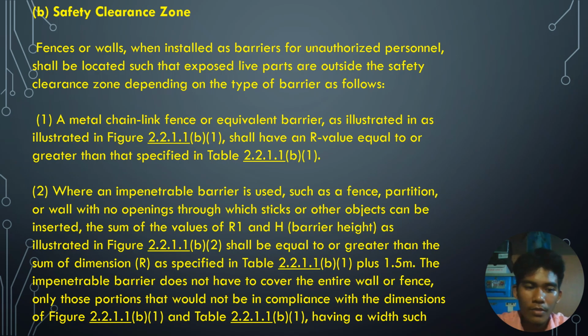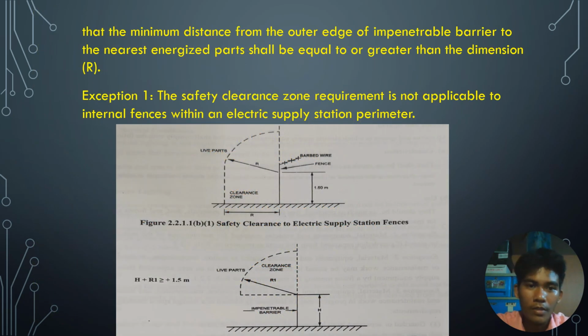in compliance with dimensions of Figure 2.2.1 and Table 2.2.1, having a width such that the minimum distance from the outer edge of the impenetrable barrier to the nearest energized part shall be equal to or greater than the dimension. Exception: the safety clearance zone requirement is not applicable to internal fences within an electrical supply station perimeter.